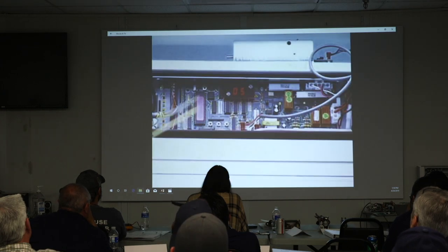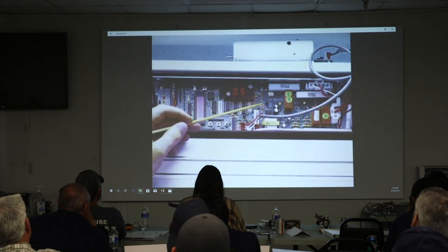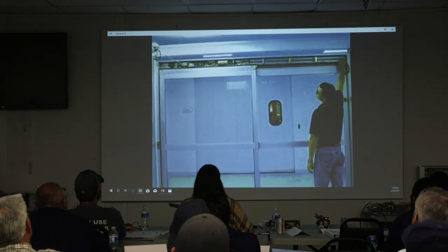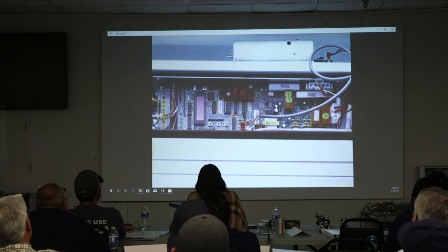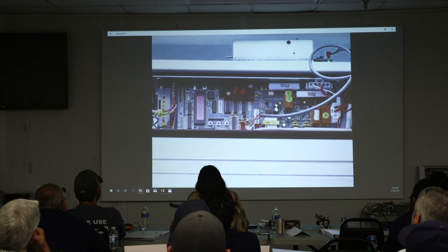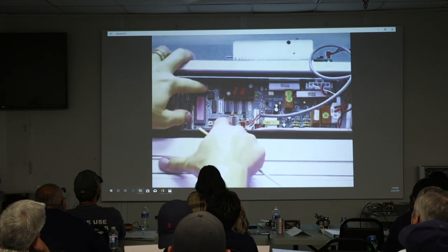Set the jumpers to linear drive setting with jumpers connected to both pins. Turn the toggle switch on and check for the toggle LED, which is the fourth LED on the left-hand side of the controller. Hold down the set and reset button simultaneously. Then release the reset button while holding the set button. The display should blink 10, then double zero. When SU displays, release the set button.